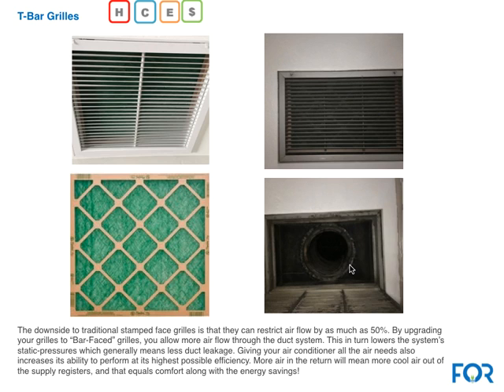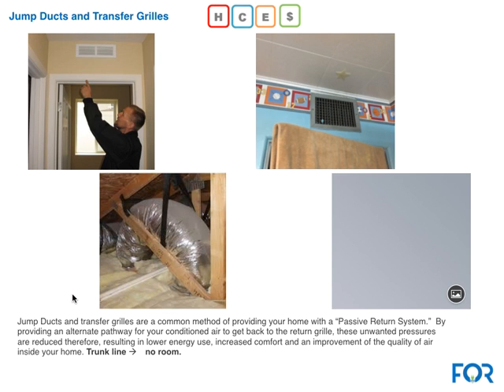Zoom in and get a couple of good pictures of leaky ducts. If the duct isn't properly sealed, hot dirty air from the attic gets pulled in around the flanges. We want zoomed-up pictures to show the homeowner that this has not been properly sealed and needs to be addressed. In this particular block, it should just be a picture of the filter.